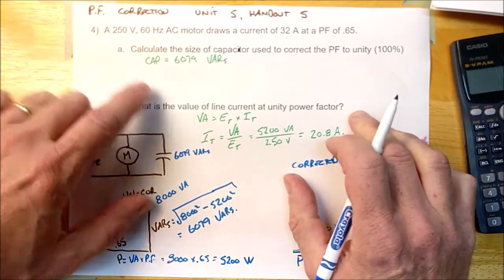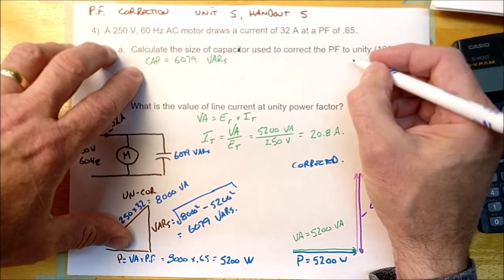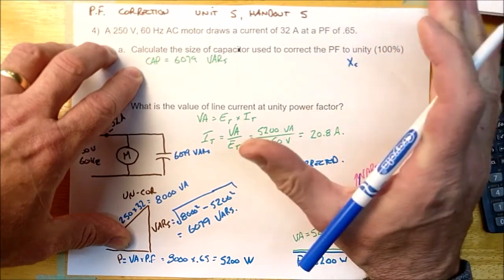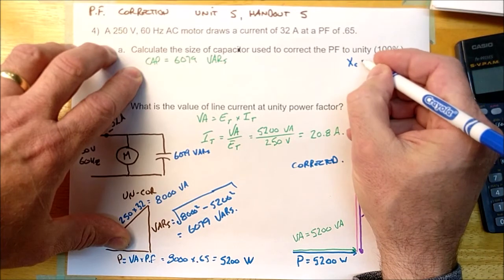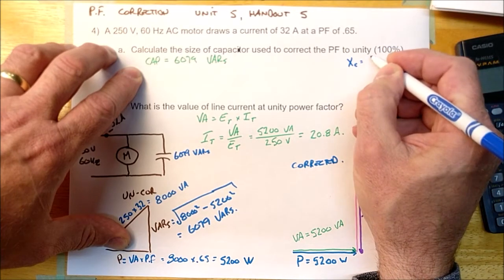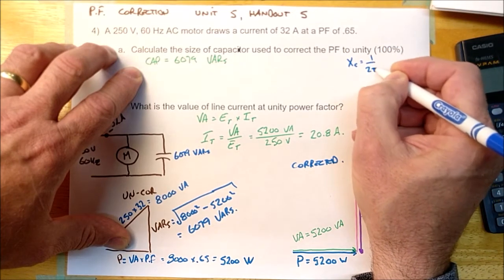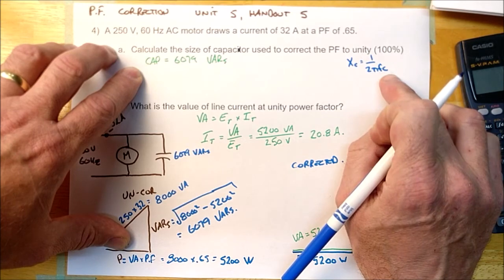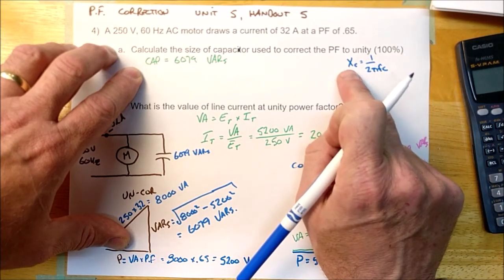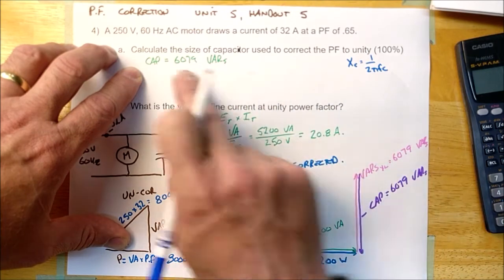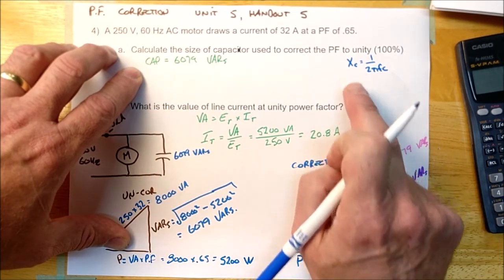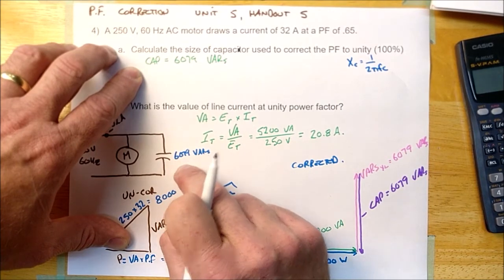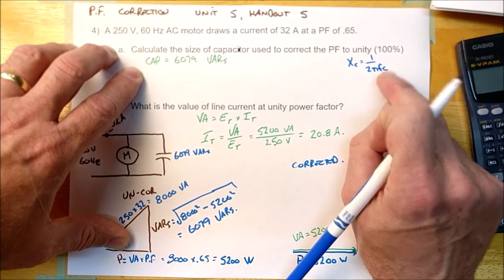So the first thing we have to understand is that this capacitor here is 6079 VARs. Now if you look at the microfarad formula, it's basically this one right here. It's XC. The only formula that I know that could work that has microfarads in it, or farads for that matter, is XC is equal to 1 over 2πFC. And C in this formula is the capacitance in farads. The only problem with this formula is I need to know XC, and I only know VARs. So the first thing I would have to do is calculate how many ohms this capacitor is. And if I can calculate how many ohms this is, then maybe I can calculate how many microfarads it is.